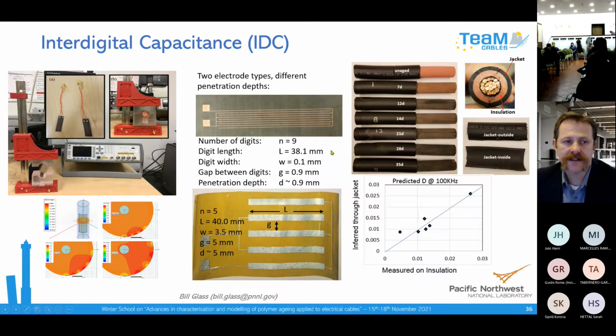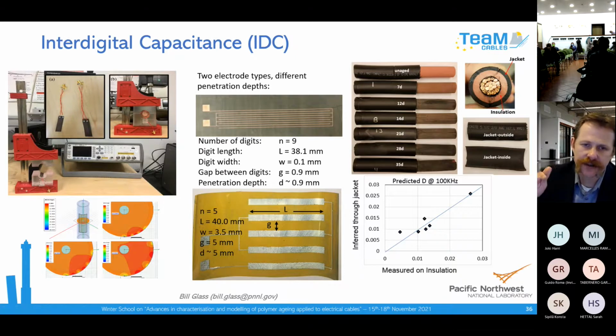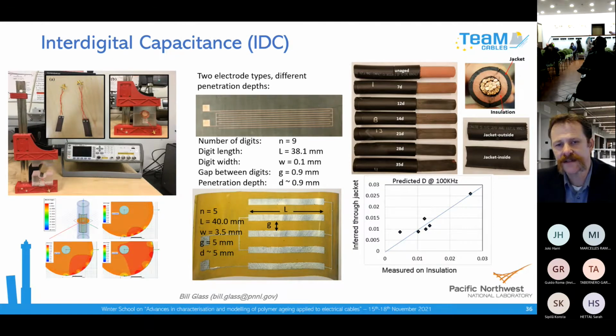Another example of this is a local technique called interdigital capacitance. This is where you have an interdigitated electrode sensor you can apply to the surface of the cable to measure the dielectric properties underneath the sensor and see if they're changing over time. This has historically been used where most cables are jacketed, to look at the change in the jacket polymer versus the insulation.